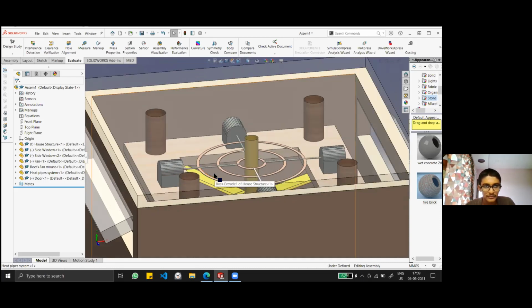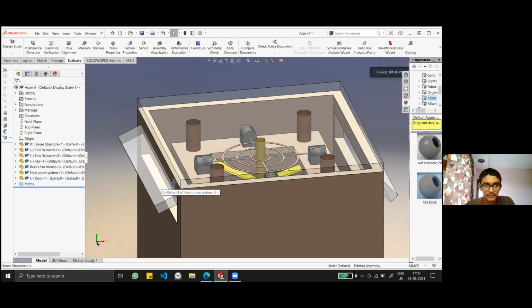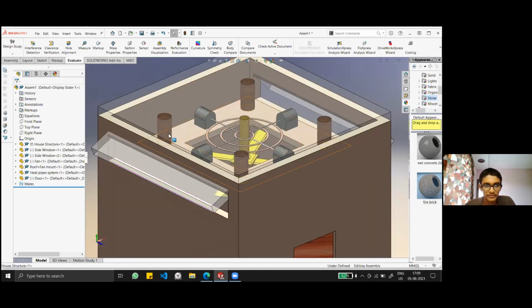An example of this phase change material is what is known as Glauber salt. It's mixed with certain additives known as freeze point depressants. So the freezing temperature comes down to around 21 degrees. That's around room temperature, a little less than room temperature, so that at night this material can be frozen, and then during the day it can melt to release the heat. This is a very simplified explanation of this whole model.